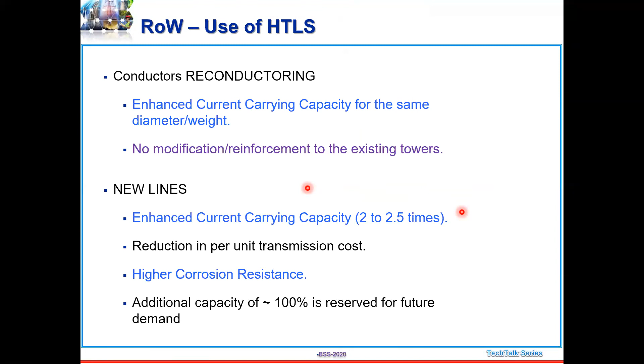So this is what happens. This is actually an ACSR. This one side is ACSR and another side is with the HTLS conductor. See here the sag is very high, but on this side with the HTLS conductor the sag is very low, but the conductor rating has gone up from 1.2 to 2 times compared to this one. So this is the main attraction of having HTLS conductor in the circuit.